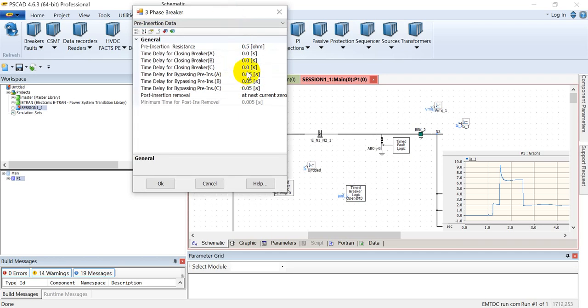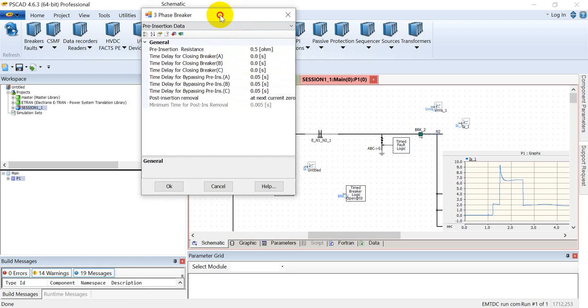Then you can also add pre-insertion resistance bypassing time delay. After this time delay, the resistance will be bypassed. Please note that this time delay will start from the instant closing pulse is given to the circuit breaker.